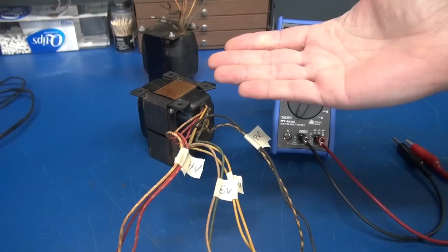Next step: after pairing up and tagging our leads, we're going to test them with an ohm meter. On the filament windings you'll see a very low resistance, as well as the primary, but the high voltage winding, since there's a lot more copper there, it's going to be maybe several hundred ohms. So we'll verify the resistance, then test each winding to the case of the transformer to verify there's no shorts. Let's start with our primary.